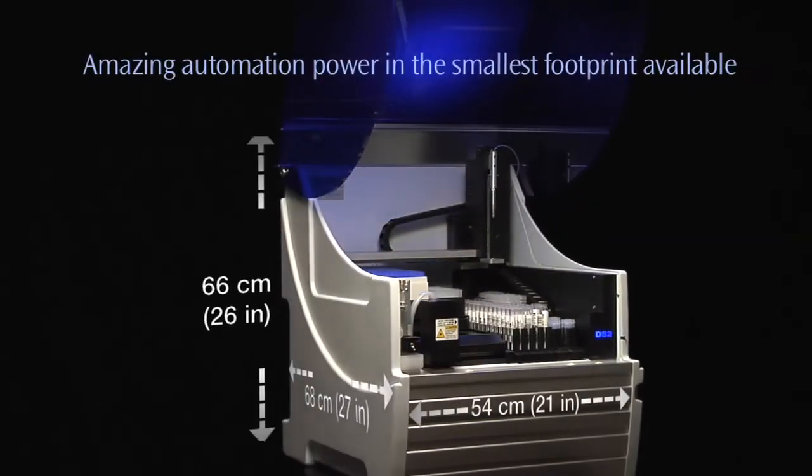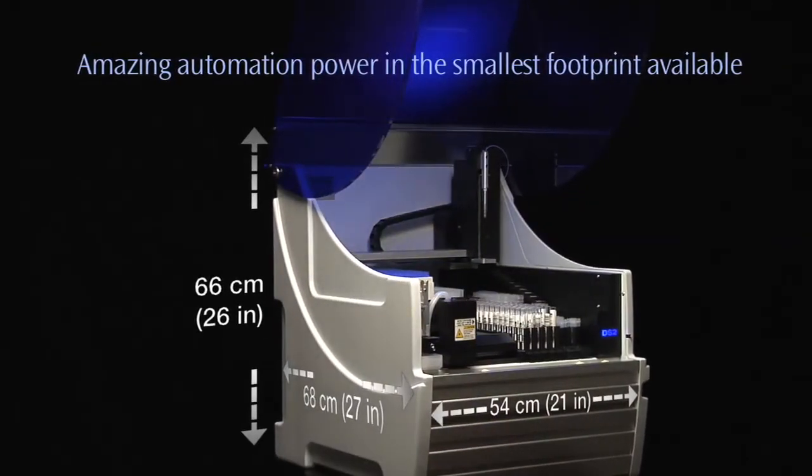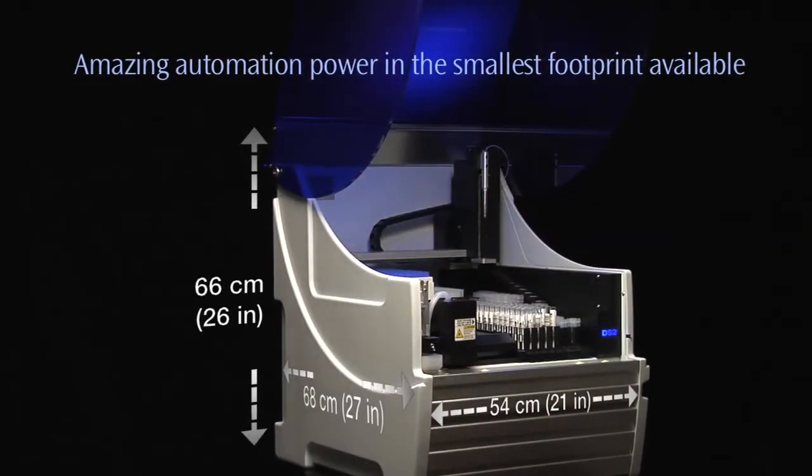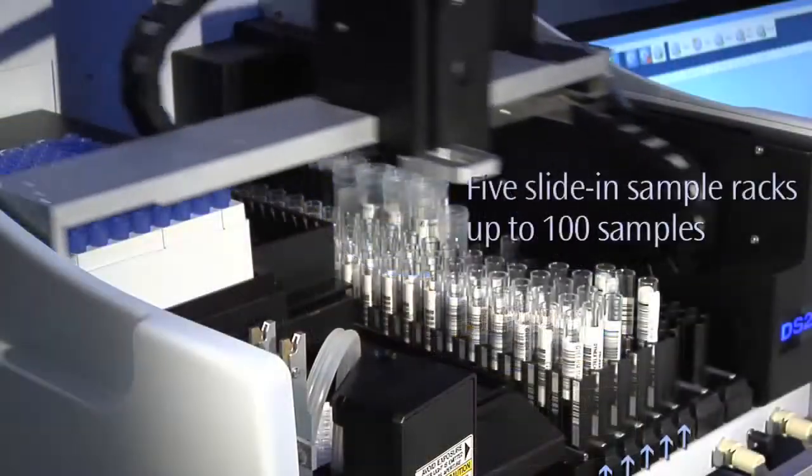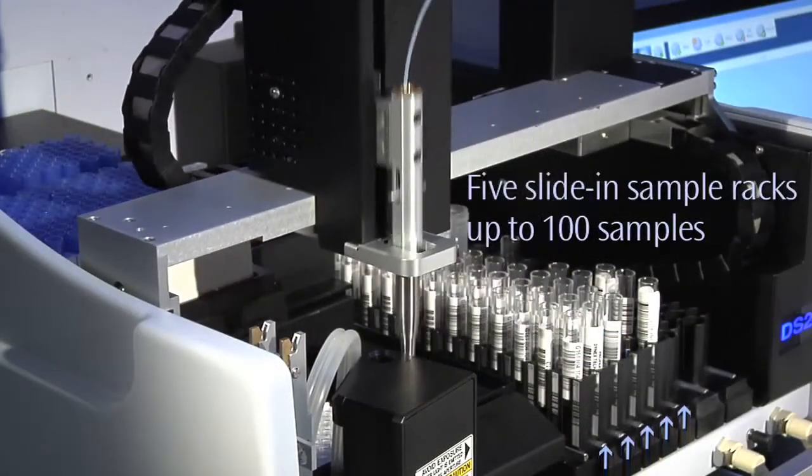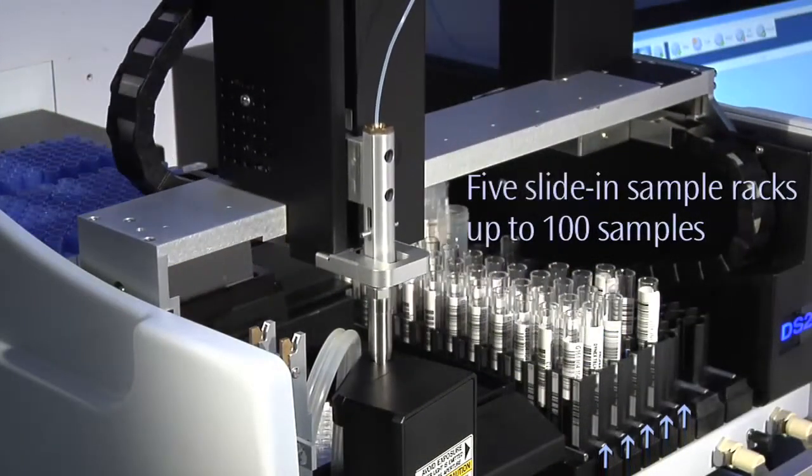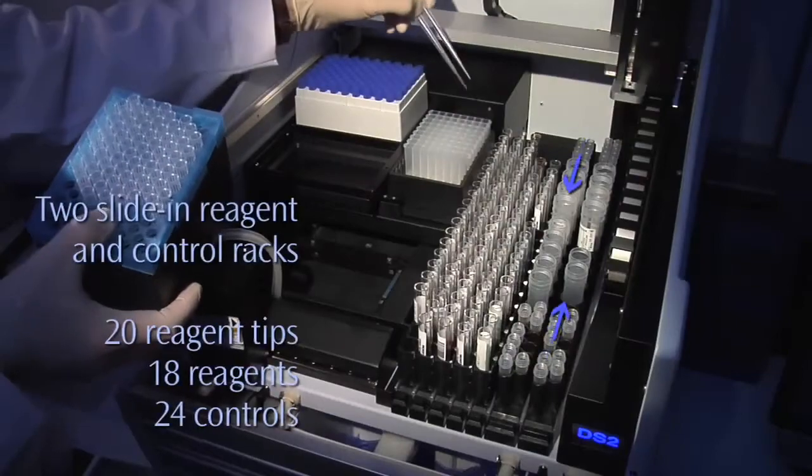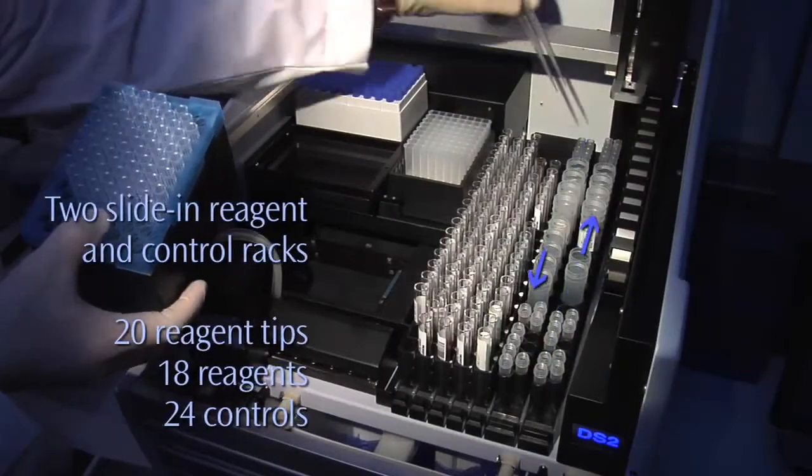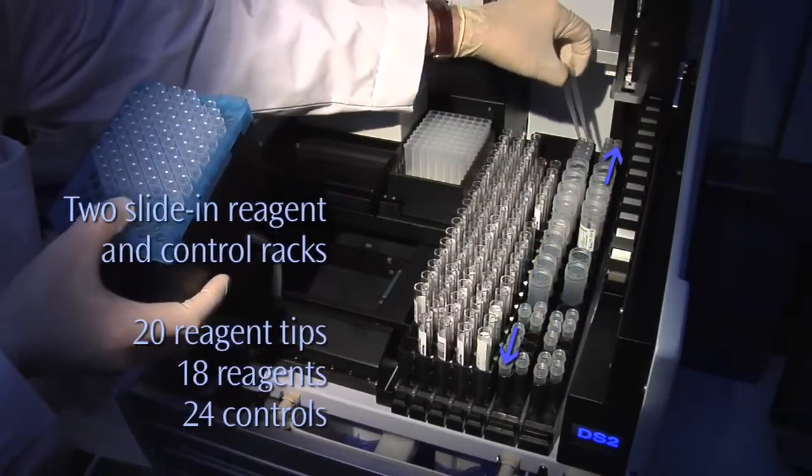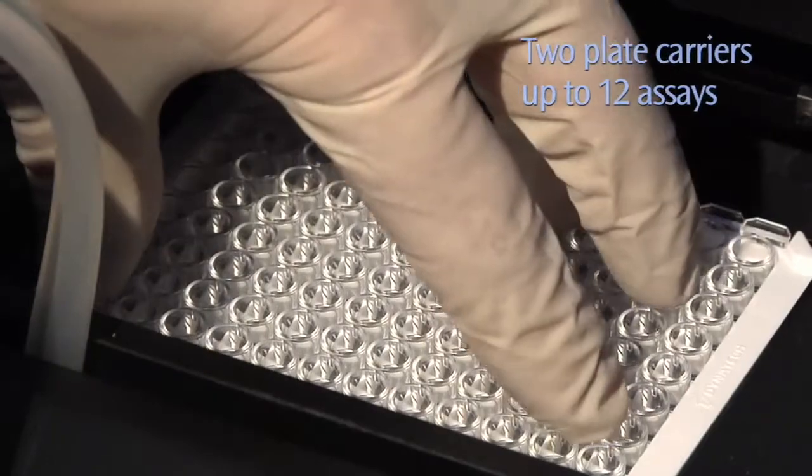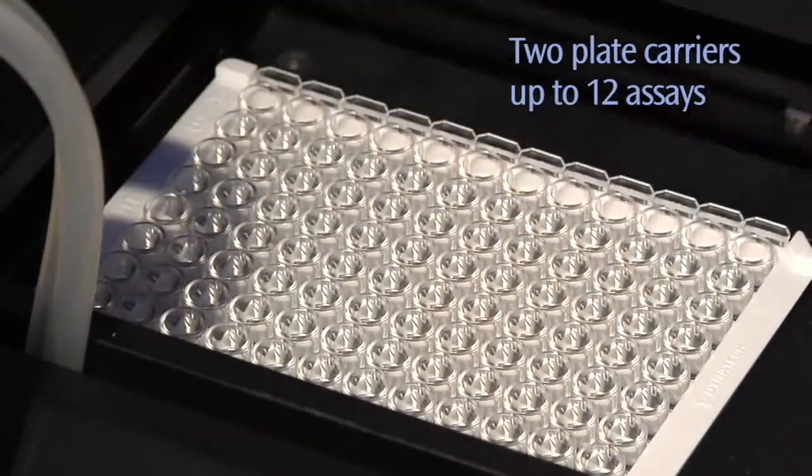The system itself takes only two feet of bench space, but offers maximum consumable storage. Five slide-in sample racks hold up to 100 samples. The DS2 has two slide-in reagent and control racks for easy consumable access. An innovative multi-plate carrier holds two 96-well microplates.